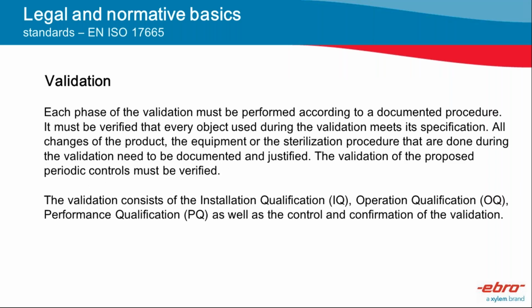So validation, therefore, is all those phases and that must be performed according to the documented procedures. So it's actually comprising all those qualification stages, the IQ, OQ, and PQ. But maybe we can put it in a way that, for Ebro, we are specifically dealing with process validations, and that's the process and the instrument. Okay, so when you say sterilization, then it's about the autoclave and about the sterilization process. So you have to remember this.